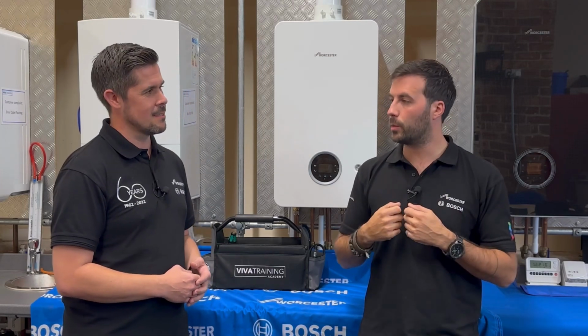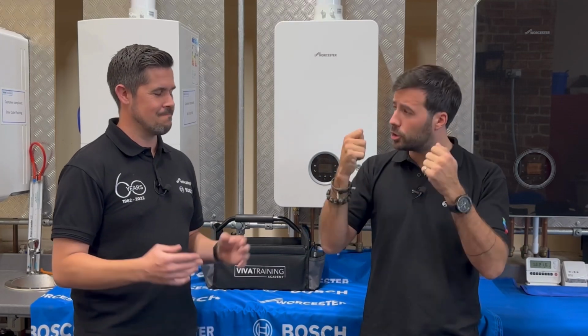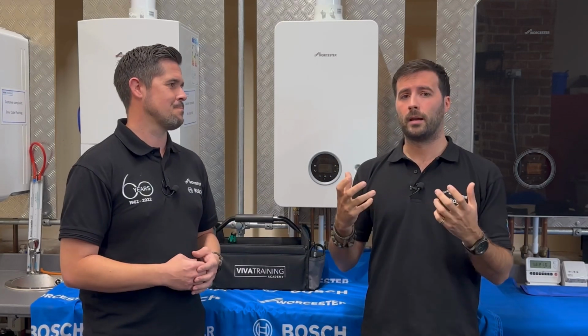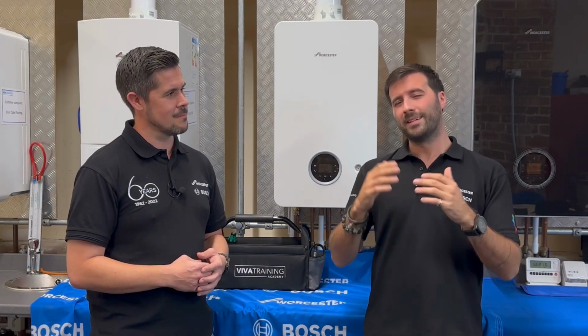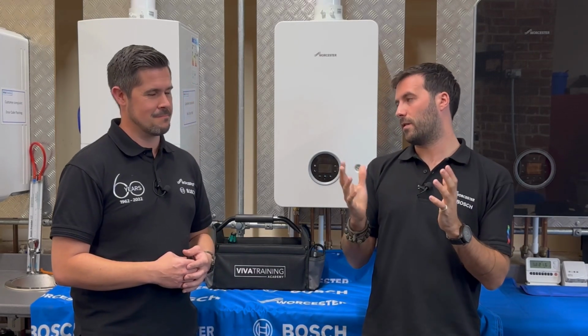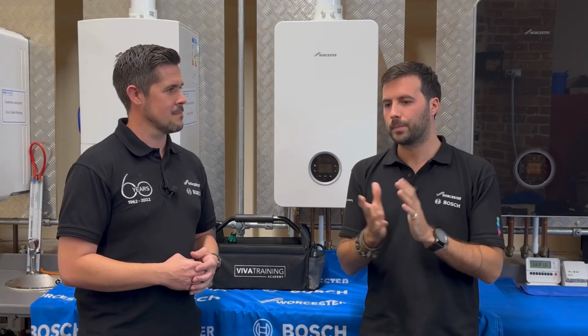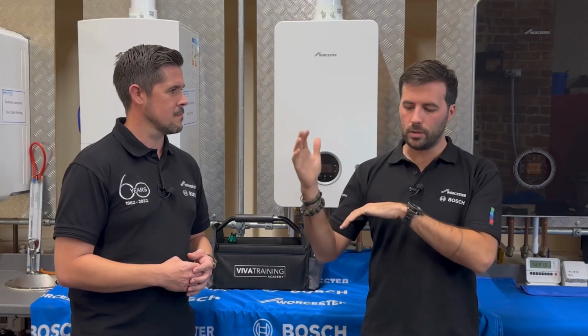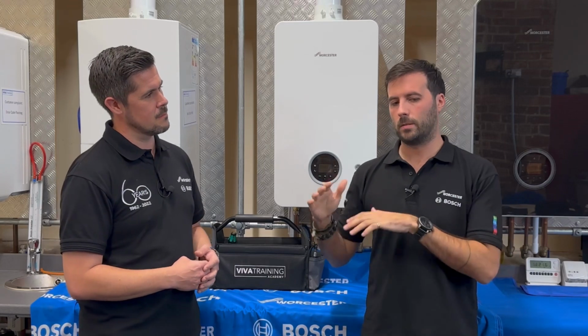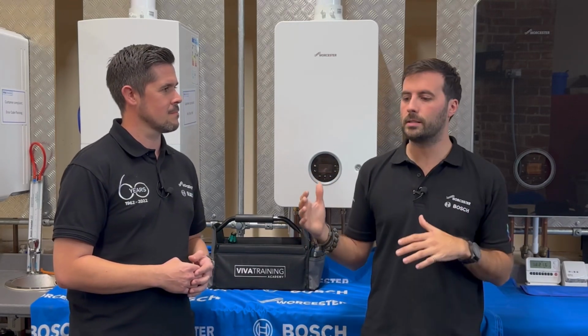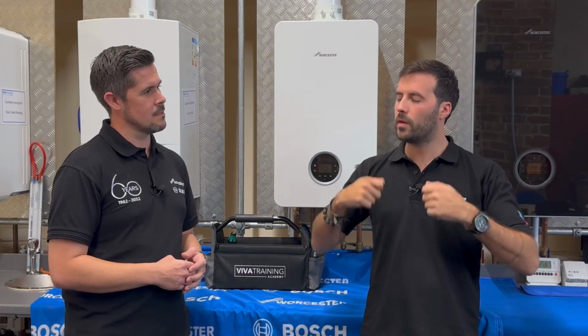And if we can make it condense, that tells us that we've extracted as much usable energy out of those flue gases as we possibly can. So the dew point is around the 55 degree mark, 53, 54, 55, something like that. So if I use low flow temperatures, I can guarantee that the boiler is condensing nearly all the time. And if it's condensing all the time, we are making use of every ounce of efficiency or of energy in there.